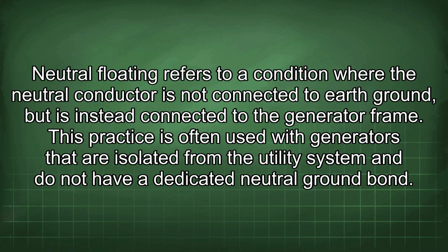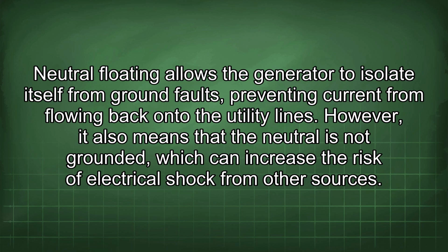Neutral floating refers to a condition where the neutral conductor is not connected to earth-ground, but is instead connected to the generator frame. This practice is often used with generators that are isolated from the utility system and do not have a dedicated neutral ground bond. Neutral floating allows the generator to isolate itself from ground faults, preventing current from flowing back onto the utility lines. However, it also means that the neutral is not grounded, which can increase the risk of electrical shock from other sources.